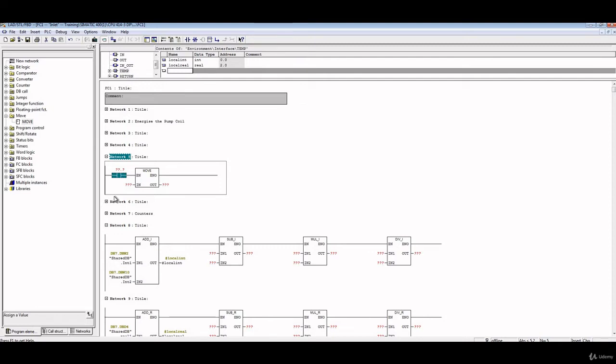Sometimes when you do a power cycle for the PLC, all the set points coming from the HMI or from SCADA are usually lost. So in some applications, we define safe operating points, or safe operating set points, that can be loaded to the program just in case of power loss. So what we usually do is, when you lose power to the PLC and the PLC is starting up, it has fresh memory and zero value for the set point.